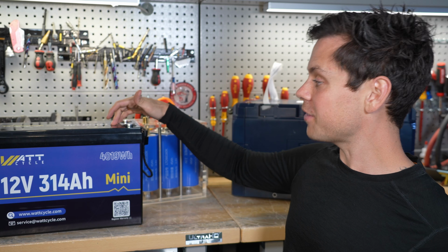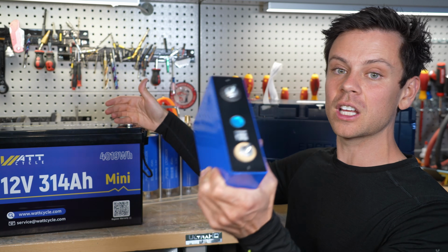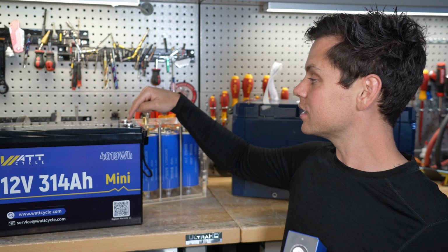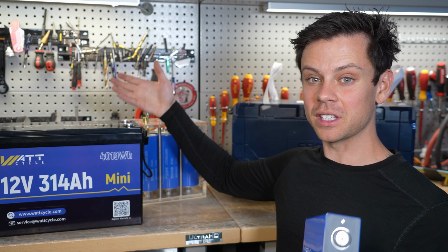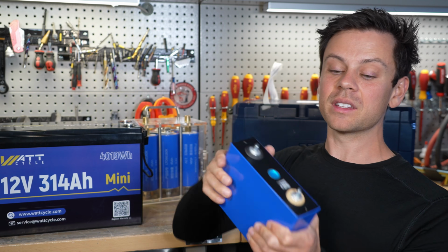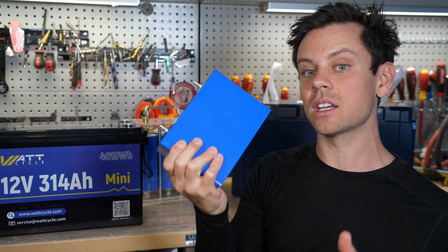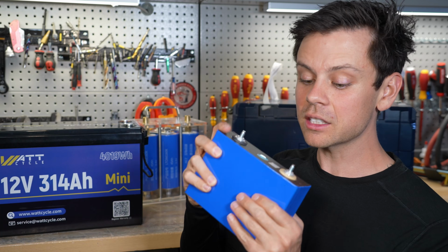When the BMS fails, it's the same as having a string of cells directly connected to the terminals with zero safety features. Once that happens, the cells are exposed to things that can cause them to vent. Once they vent, they give off white smoke, and that smoke is very bad for your health.